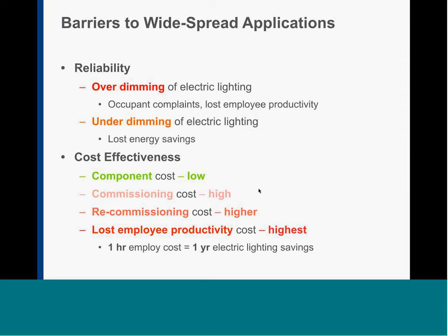That's where again I have to bring a person to do it. That cost is the highest cost today, and of course the loss of employee productivity because they get disturbed by that is even higher. You can see there the equation. This is why another study that happened with the HMG group about a decade ago, I think, found that half of the daylight harvesting systems, or to be accurate, electric lighting control systems for daylight harvesting, are disabled by the people, and the ones that work use less than 50% of the expected savings.